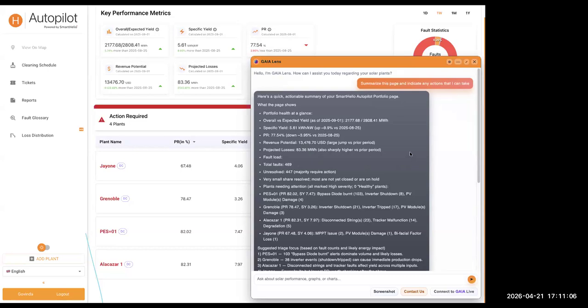Let's say today I used it to check an error about the curtailment, and I saw that some strings were giving negative values and an error of string reverse feedback. So I was trying to see how harmful this can be and how we can track it.